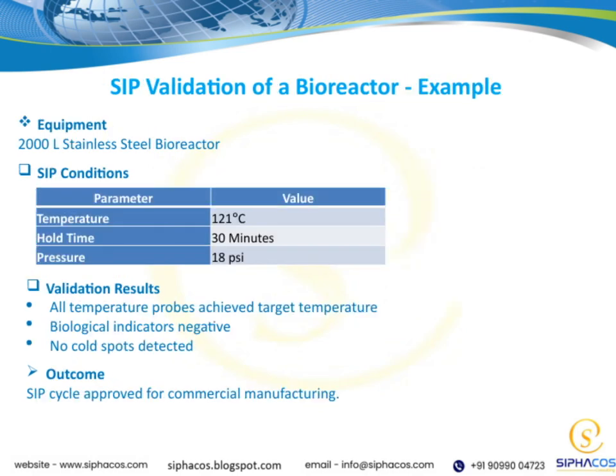Let's look at the validation results for the sterilization in place cycle. Every temperature probe hit the target temperature, confirming uniform heat distribution. Biological indicators came back negative, so no contamination survived. We also found no cold spots anywhere in the system. With these results, the SIP cycle is approved for commercial manufacturing. This example used a 2,000-liter stainless steel bioreactor, running at 121 degrees Celsius, held for 30 minutes under 18 psi pressure. This validation ensures consistent, reliable sterilization every time.